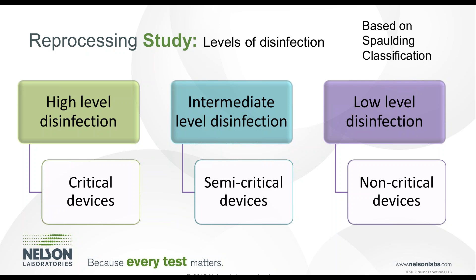An example of that would be a blood glucose meter — it's non-patient contacting, but you need intermediate level disinfection because of exposure to blood. A low level disinfection example would be non-patient contacting, non-critical devices such as IV monitors, bed rails, non-porous surfaces — things that wouldn't contact the patient and are non-critical.